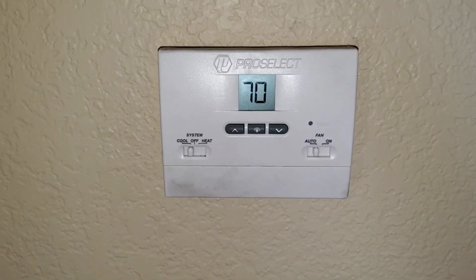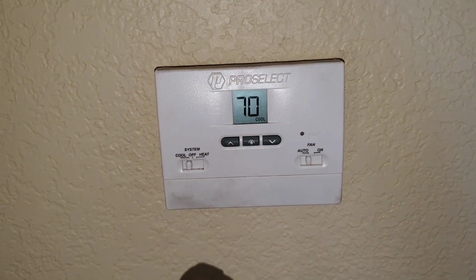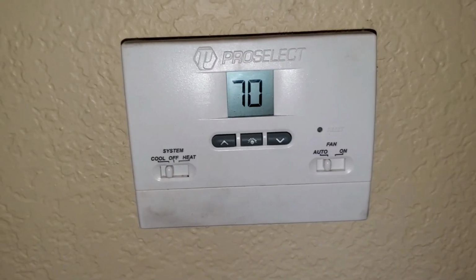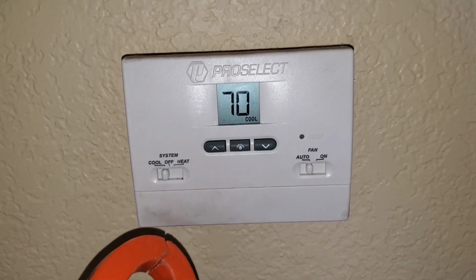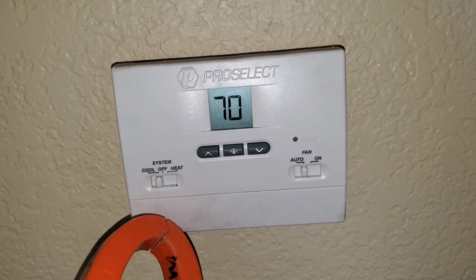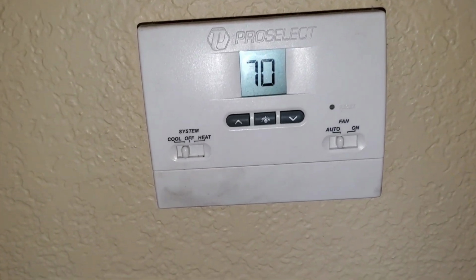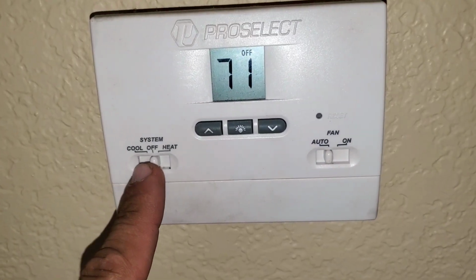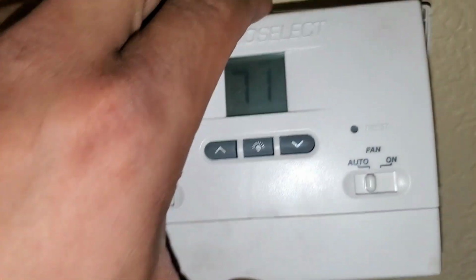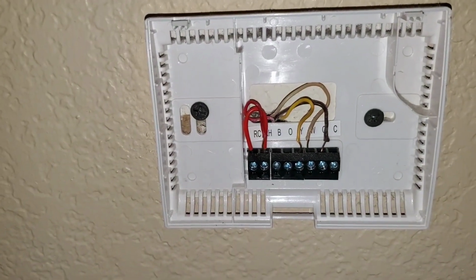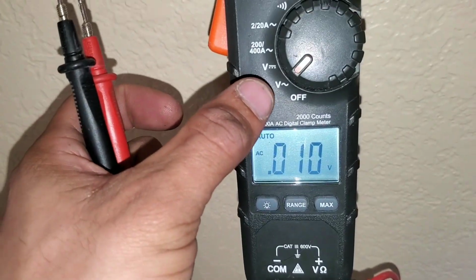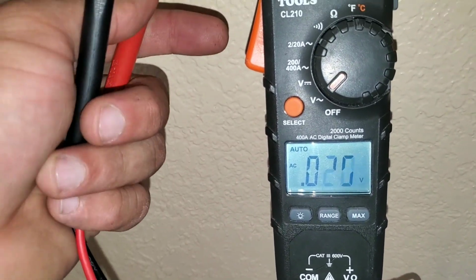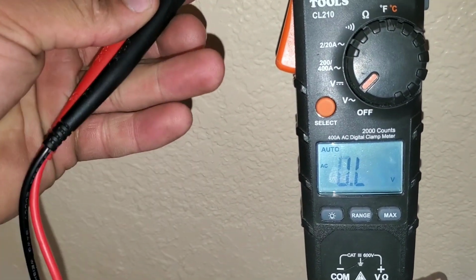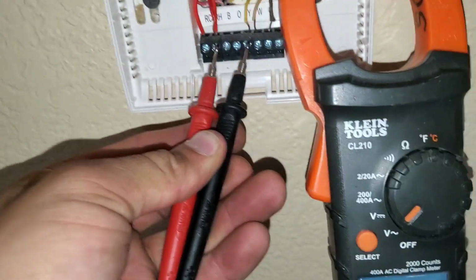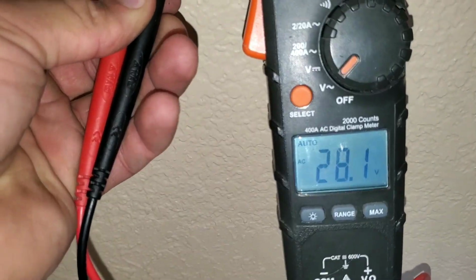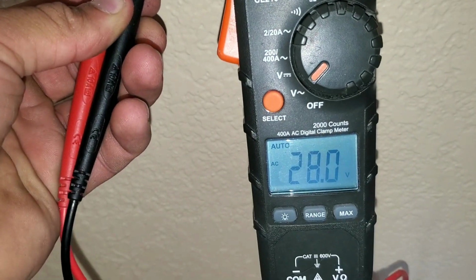At this point, we're confident that the problem's between step one and step two. The next thing I'm going to do is remove my cover for my thermostat, and check voltage at my thermostat. Here, I set my thermostat to off, and we're going to check for voltage. Multimeter set to volt AC. I'm going to put one lead for my multimeter on my R terminal and one on my Y terminal, and I should get voltage, which I do have voltage coming in.